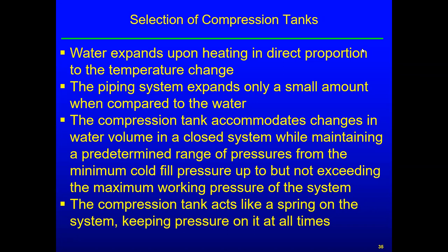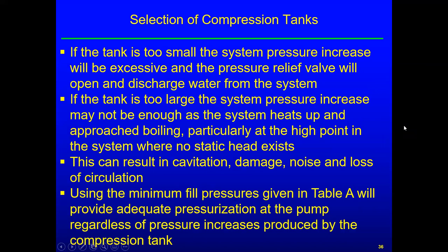So a compression tank acts like a spring on the system, keeping pressure on at all times. If the tank's too small, we get an excessive pressure increase, and we maybe start blowing water out of the system, which we really don't want to do. If the tank's too large, the pressure increase may not be enough as the system heats up, and it's possible that we could actually get cavitation in the pump. Probably not likely, but theoretically at least it's possible.